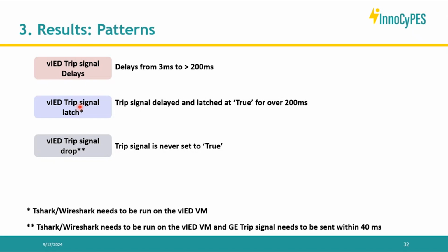Which means that the value of the trip stayed true for sometimes over 200 milliseconds, saying that you should keep it open because of this delay in treating the signal due to having barely any access to the resources during this attack. And the last one, the most extreme case, is that the virtual IED never even detects the fault and doesn't even send a trip.